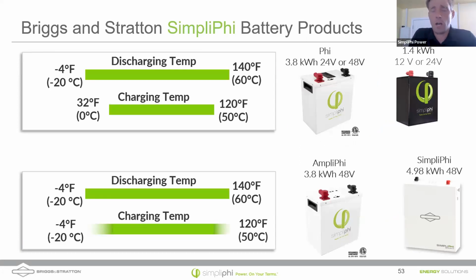So let me get to this slide that Daniel was asking about earlier, that somebody had asked about earlier, and Daniel was referring to. So for our non-communicating batteries, the PHI batteries, we're really limited in our temperature range to 0. We can't charge below 0, and that's because the lithium has a really hard time getting into the graphite. And so it can build up and even form what are known as dendrites or branches. It's basically solid lithium deposits that can damage the cells over time. So it's important, if you have non-communicating batteries, that you do something if you're in a cold environment to make sure that the charging equipment doesn't try to push charge in cold temperatures.